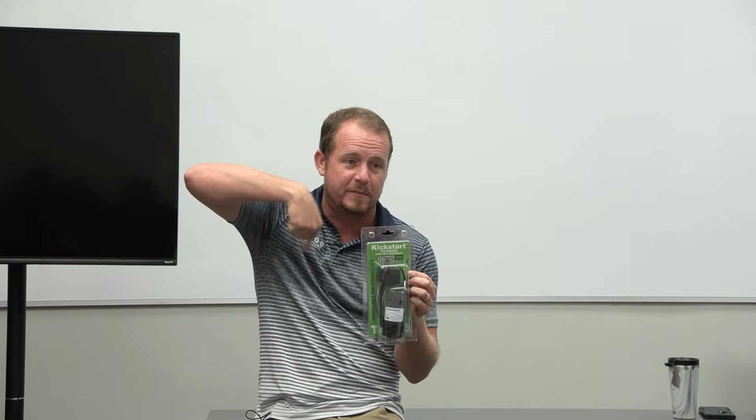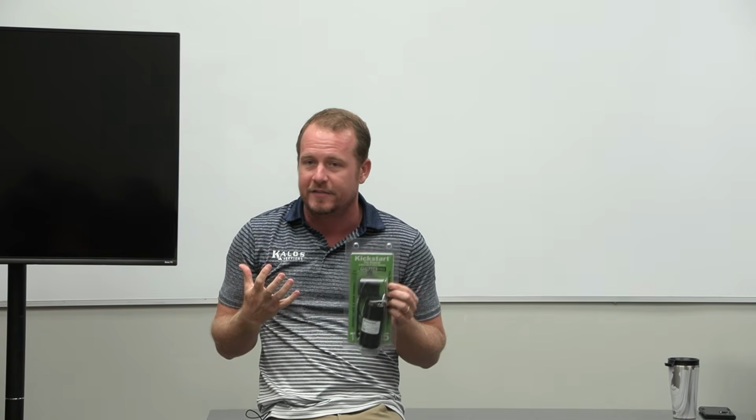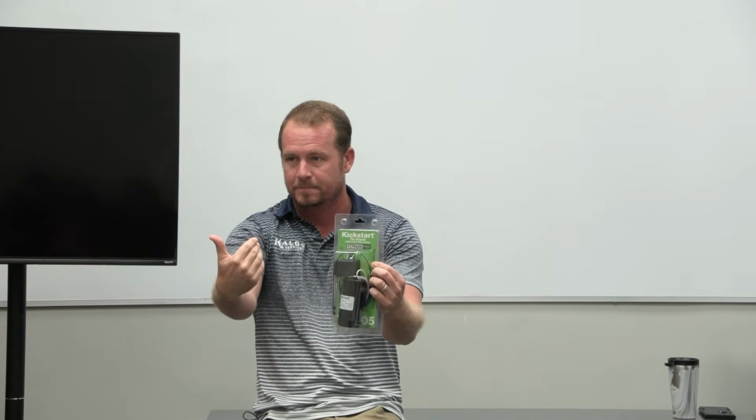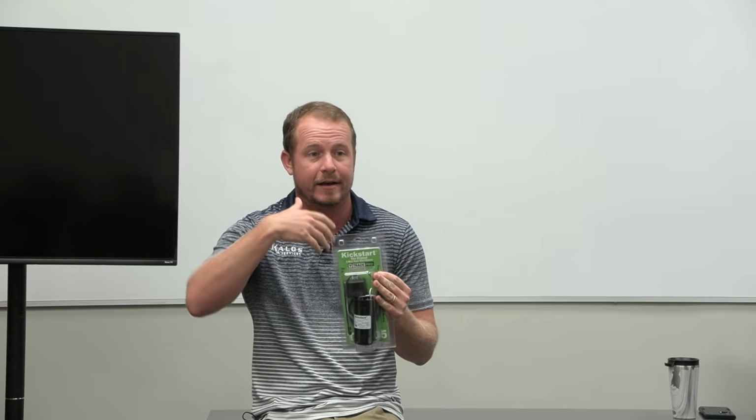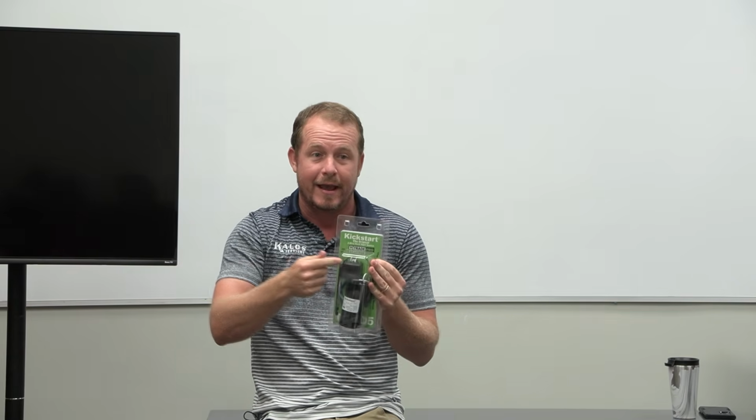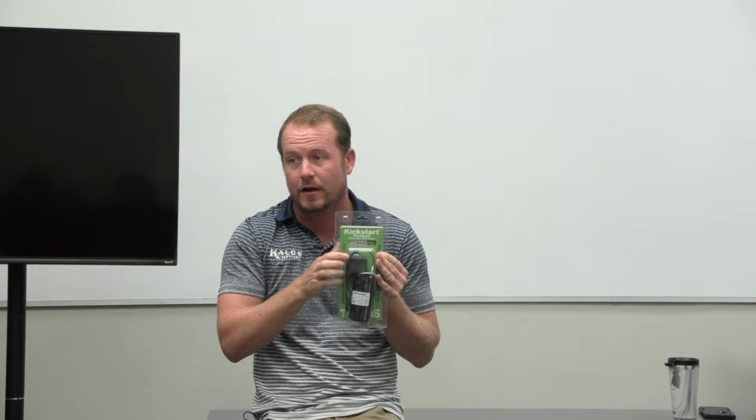When that motor starts spinning, it not only receives current, it also produces its own energy. It acts simultaneously as a motor and a generator, because it has this rotating magnetic field and there's an interaction between the rotor and the stator. So it creates something called back EMF. That back electromotive force increases as the motor spins faster, and that's what energizes the relay on this potential relay.